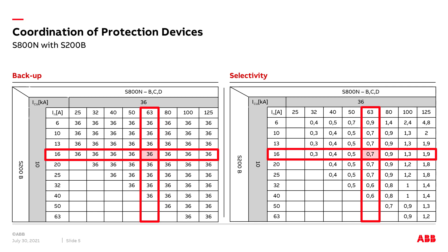Here you see the two tables of backup protection and selectivity for the upstream breaker S800N and the S200 as downstream breaker in comparison. If the upstream S800 is selected with a nominal current of 63 amperes and the downstream S200B with 16 amperes, the backup protection would be 36 kilo amperes — even though the S200 only has 10 kilo amperes. However, the selectivity level would be only 700 amperes, meaning the S800 will not trip as long as the short circuit current is less than 700 amperes.